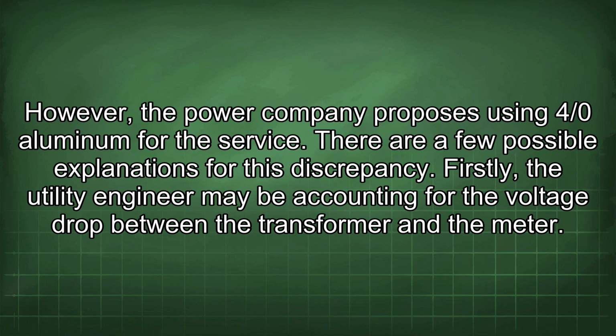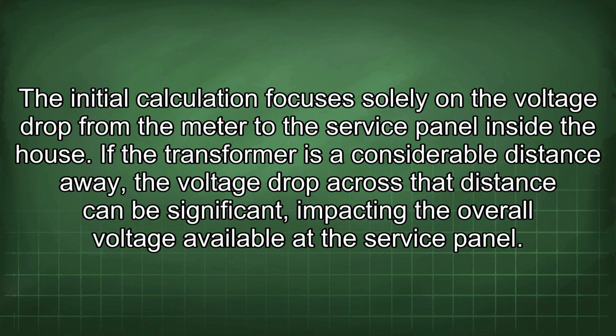There are a few possible explanations for this discrepancy. Firstly, the utility engineer may be accounting for the voltage drop between the transformer and the meter. The initial calculation focuses solely on the voltage drop from the meter to the service panel inside the house. If the transformer is a considerable distance away, the voltage drop across the distance can be significant, impacting the overall voltage available at the service panel.